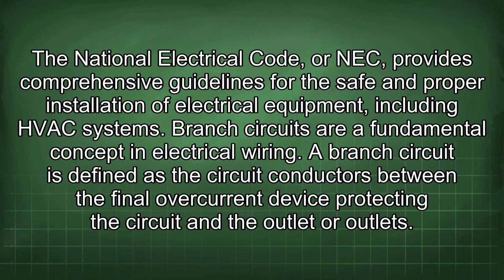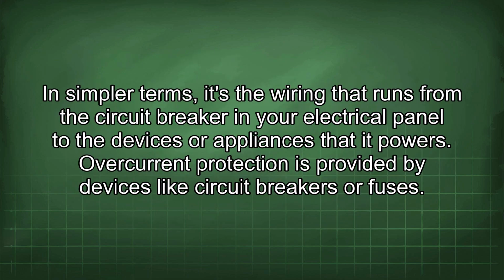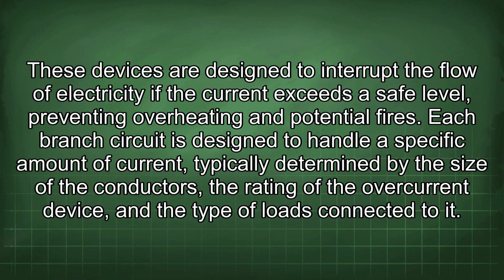A branch circuit is defined as the circuit conductors between the final overcurrent device protecting the circuit and the outlet or outlets. In simpler terms, it's the wiring that runs from the circuit breaker in your electrical panel to the devices or appliances that it powers. Overcurrent protection is provided by devices like circuit breakers or fuses. These devices are designed to interrupt the flow of electricity if the current exceeds a safe level, preventing overheating and potential fires. Each branch circuit is designed to handle a specific amount of current, typically determined by the size of the conductors, the rating of the overcurrent device, and the type of loads connected to it.